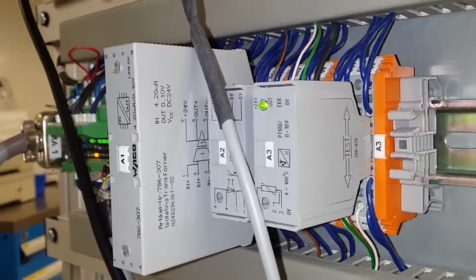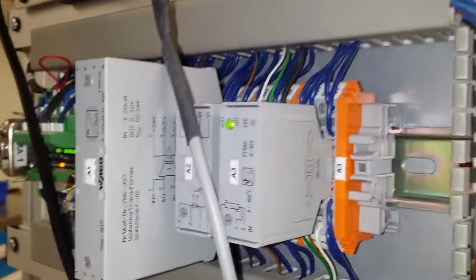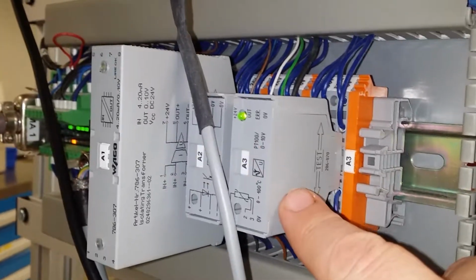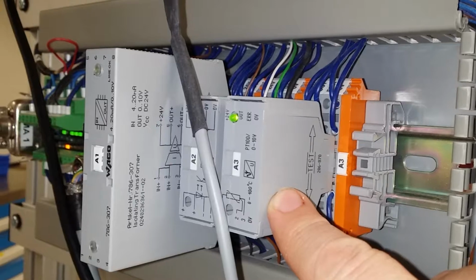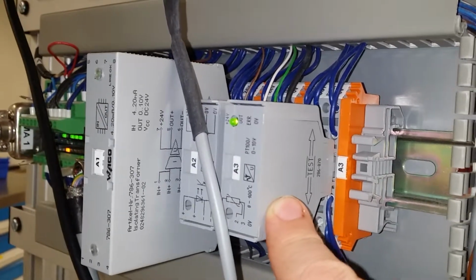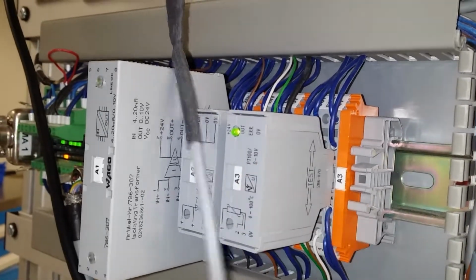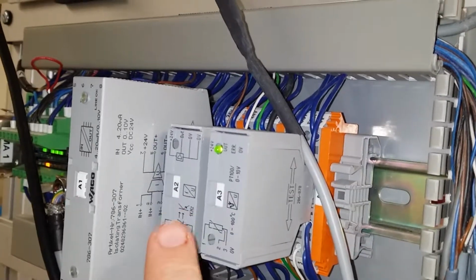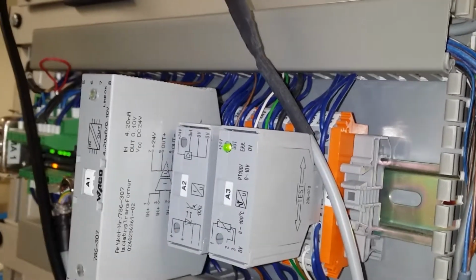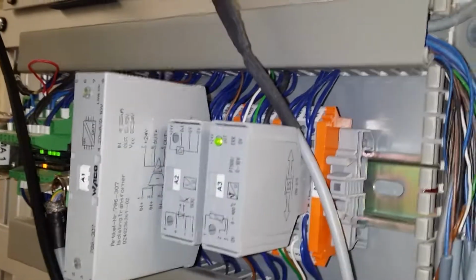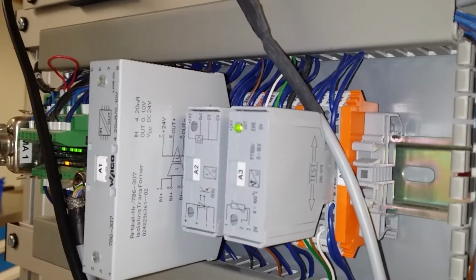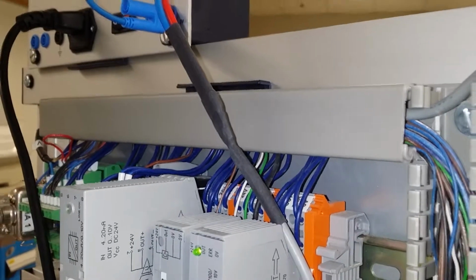And while I'm here, I want to point out the modules for each of the converters. This is the one that converts the RTD signal from 100 to 138.5 to 0 to 10 volts. The next module over is for the converting of the frequency from the flow sensor. The third module over is the one that converts the 4 to 20 from the level sensor to 0 to 10 volts out.